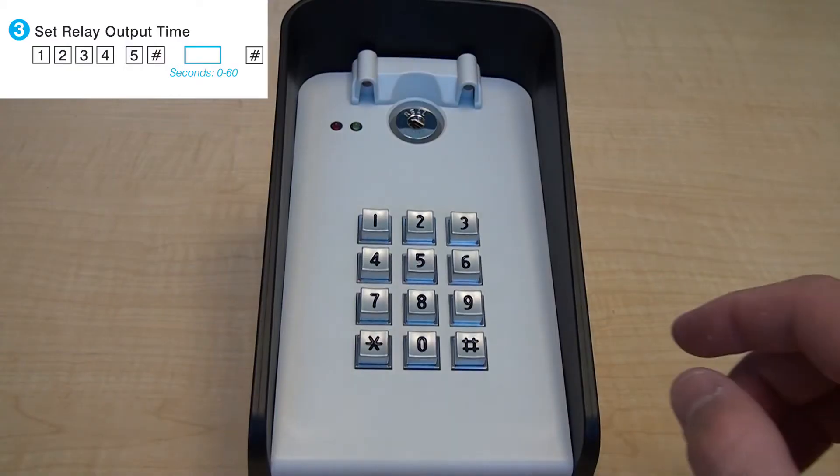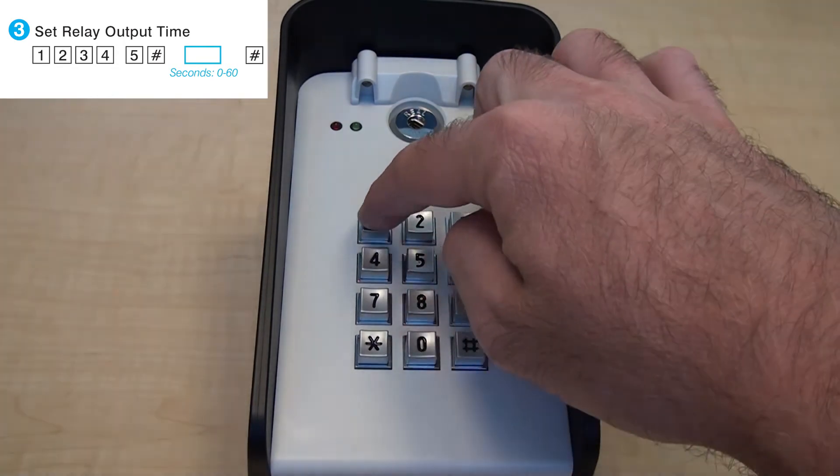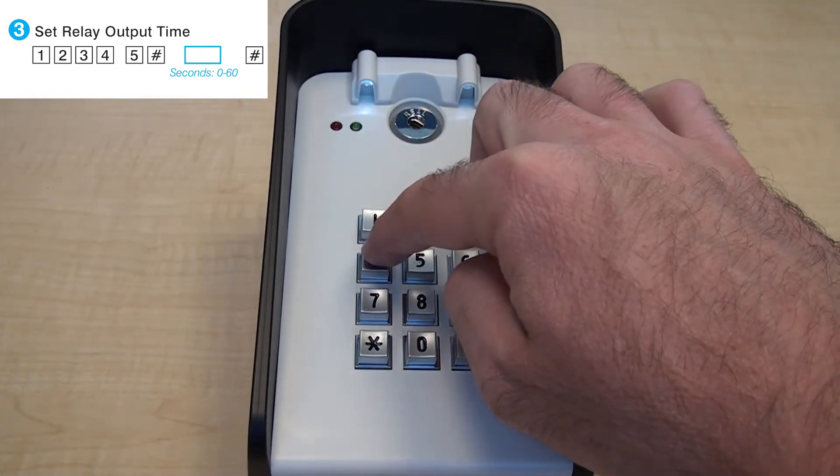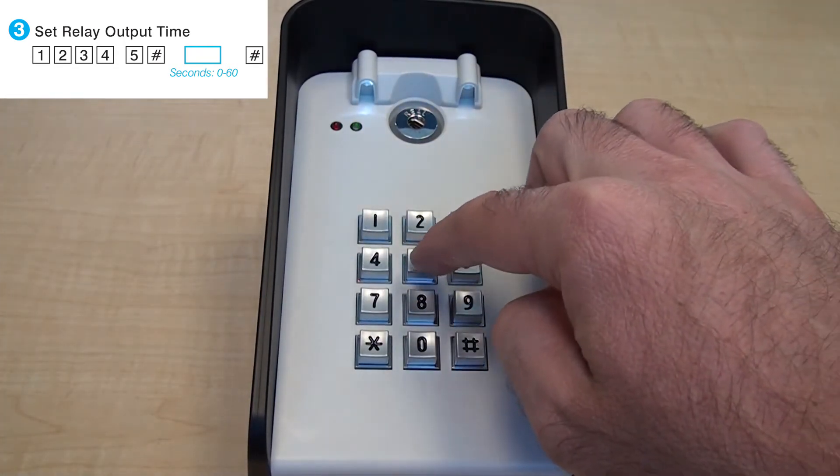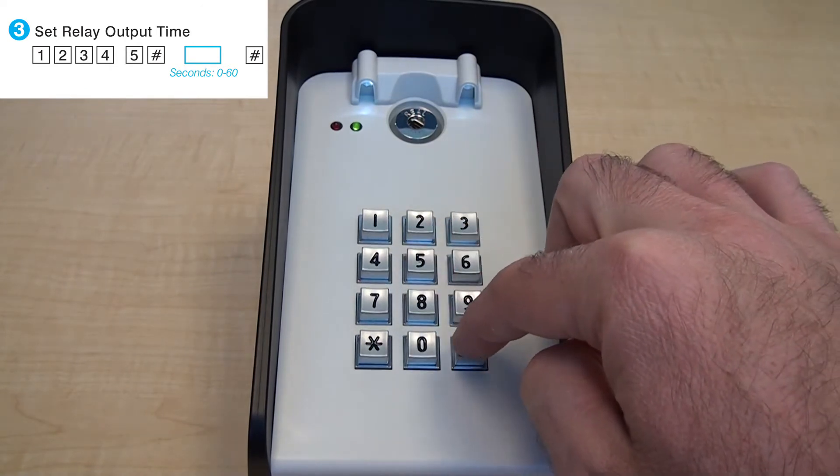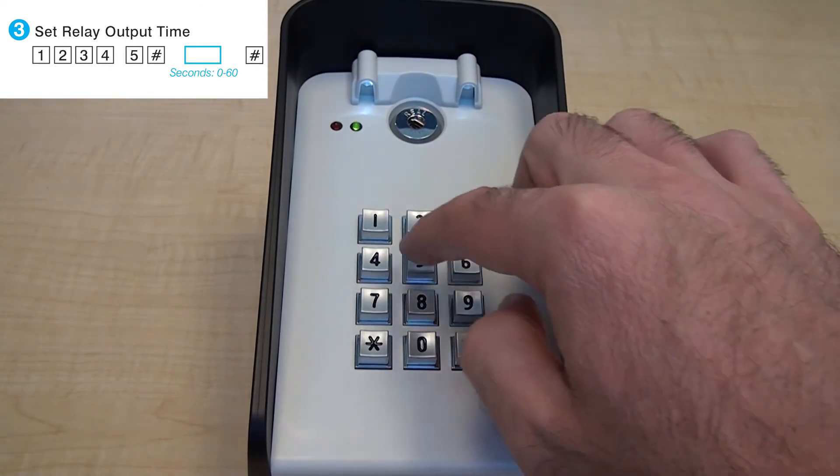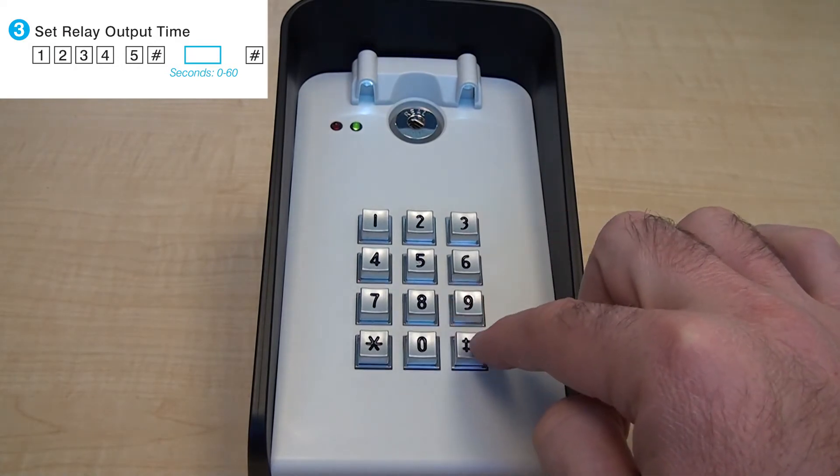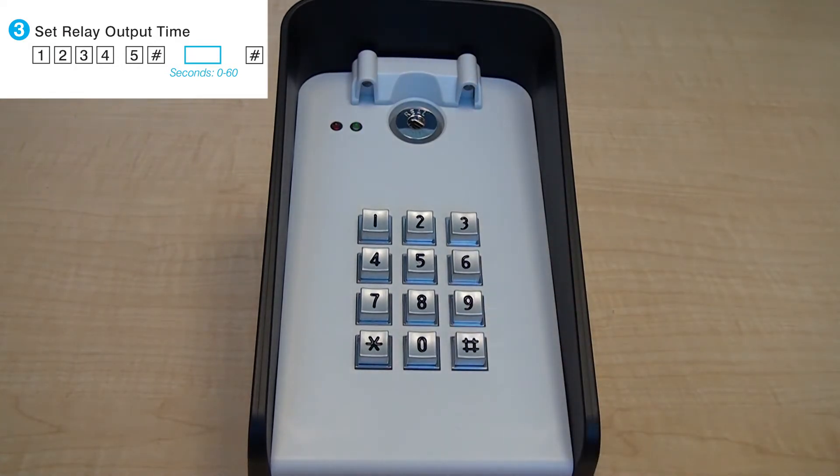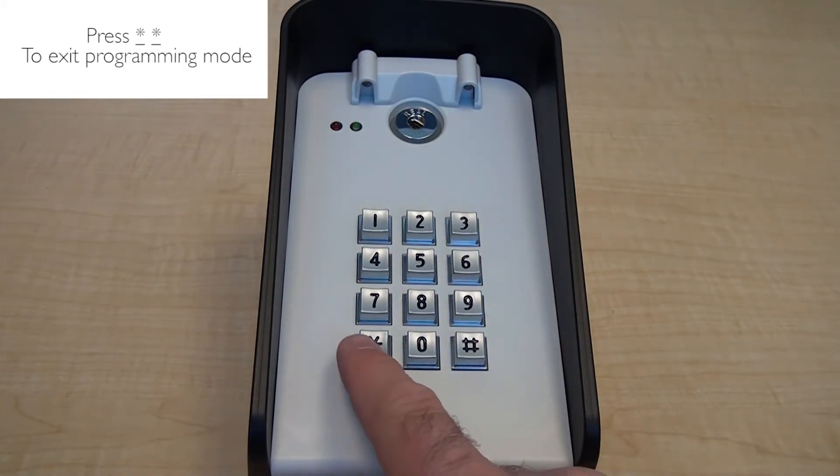To set the relay 1 output time, first use the master code to enter programming mode. Press 5 pound to enter the relay function in the keypad. Choose the relay output time between 0 and 60 seconds followed by the pound sign. When finished, press the star button twice to exit programming mode.